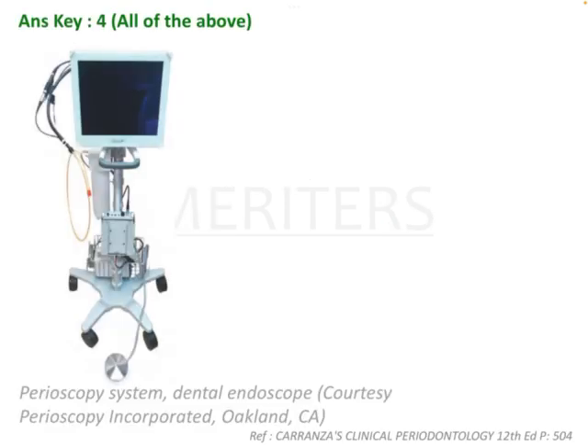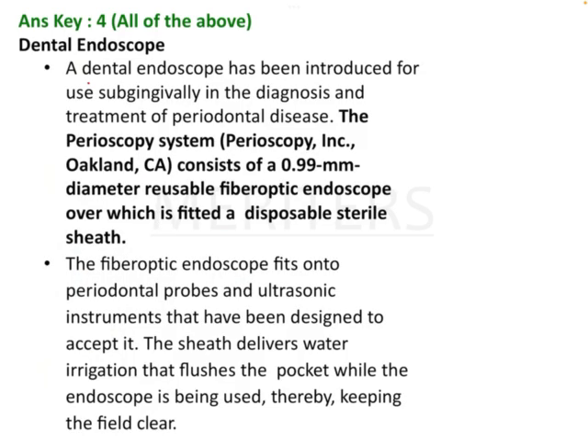This is how a perioscope looks clinically — the visualisation is done on the screen while the tip goes into the sulcus, helping in visualisation of furcations and the sub-gingival pocket. A dental endoscope has been introduced for sub-gingival diagnosis and treatment of periodontal disease via the perioscopy system. It consists of a 0.99 mm diameter reusable fiber optic endoscope with a disposable sterile sheath.